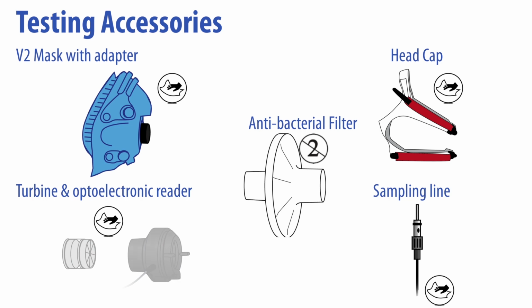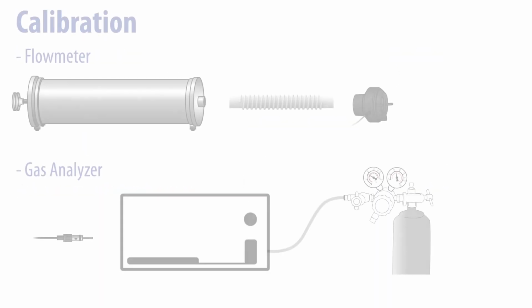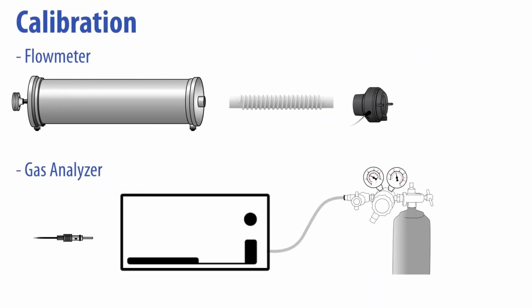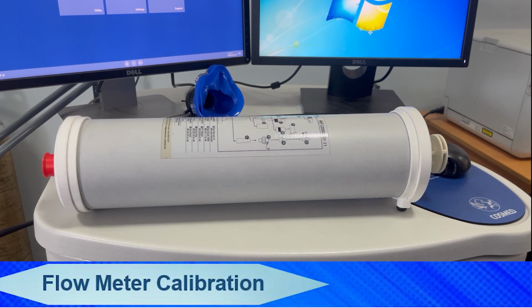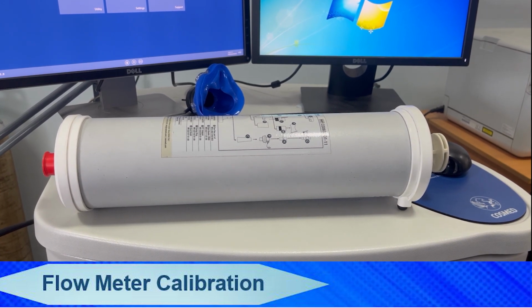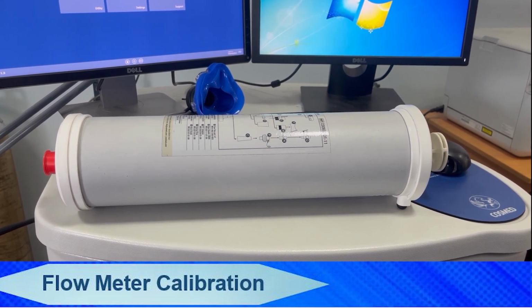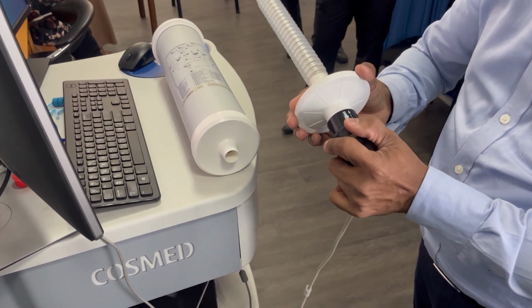All CPET systems should be calibrated immediately before each test, including the oxygen analyzer, carbon dioxide analyzer, flow meter, cycle ergometer or treadmill, and blood pressure transducer. Normally, volume calibration and verification of the calibration is done with the aid of a 3-liter calibration syringe.